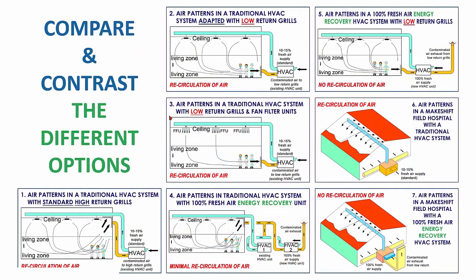We've looked at different options to adapt our system, so let me give you a small recap. First, a traditional HVAC system with high return and ceiling diffusers. Then the same system with lowered return grills, which changes the air pattern. Then a situation where we replaced the ceiling diffuser with fan filter units and a low return. Then a situation with a 100% fresh air unit with energy recovery, and another option where a 100% fresh air unit replaced the existing HVAC unit. Finally, we looked at two field hospital systems: one with recirculation and another with 100% fresh air.